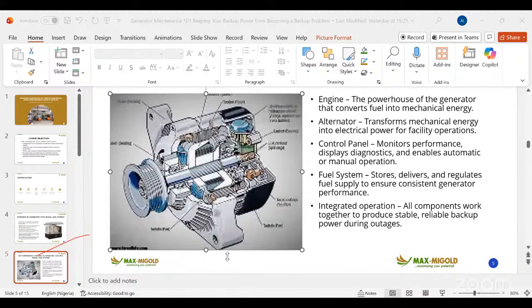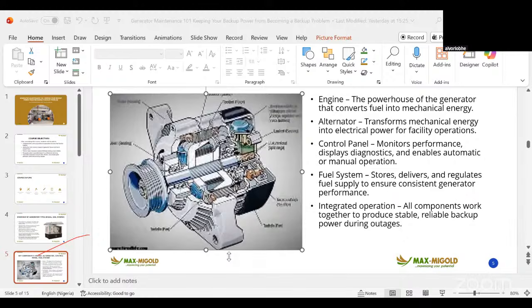I'm here, sir. Okay. Maybe your aggregate load is 1,000 kilowatts. For you to get kVA, you divide that 1,000 by 0.8, that's the power factor. You are converting to kVA, and it gives you 1,250 kVA. So that's the exact generator load demand for your facility. You cannot recommend exactly 1,250 for your facility. You can give an allowance. Let's say you push it to about 1,600 kVA. You are giving an allowance.